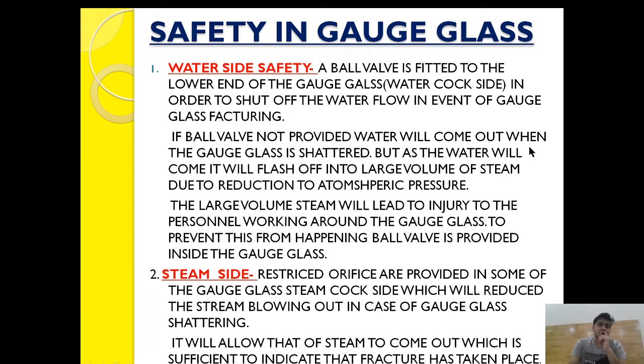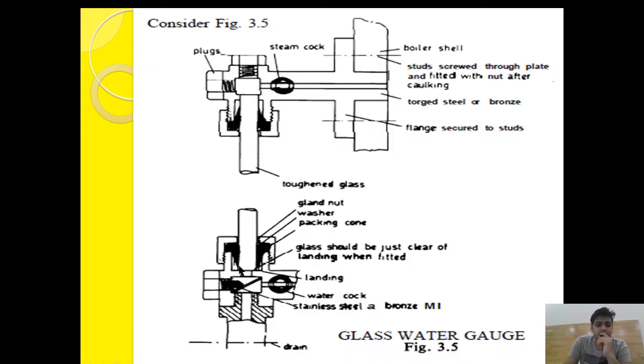First, let's see the water side safety. A ball valve is fitted to the lower end of the gauge glass water cock side in order to stop water flow in the event of glass fracturing. A stainless steel or bronze ball is provided in the lower section of the water cock so that if the glass fractures, this ball valve acts as a non-return valve to prevent water from gushing out.